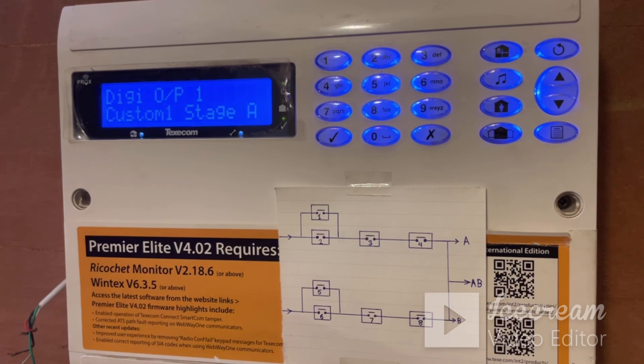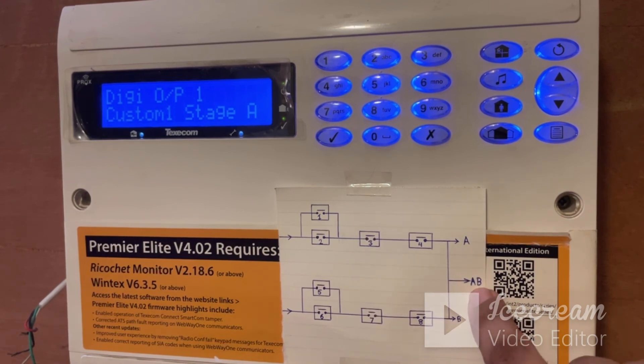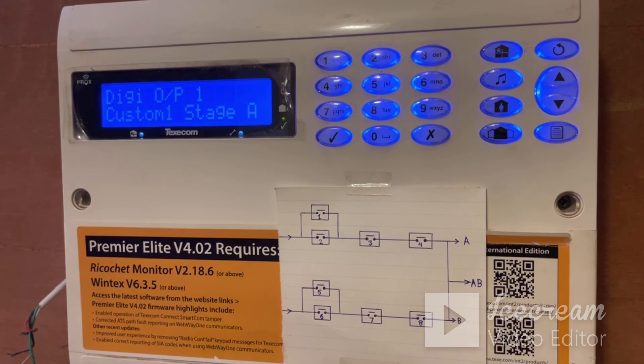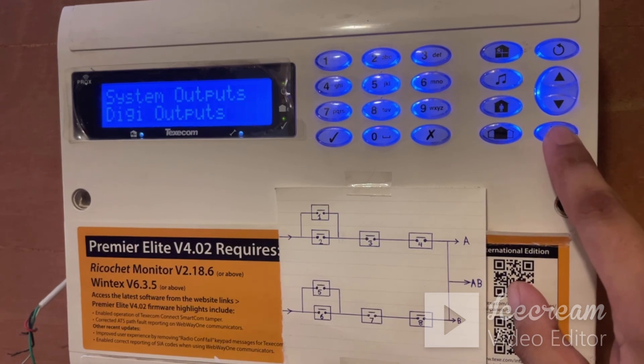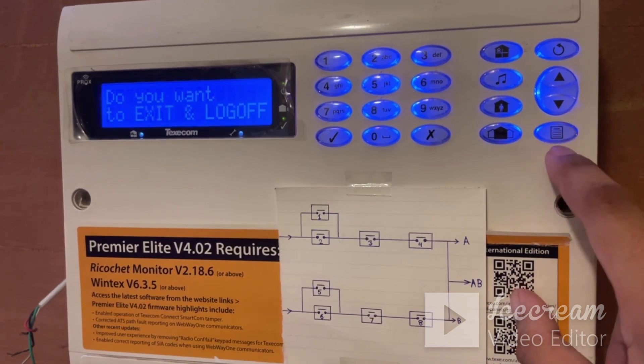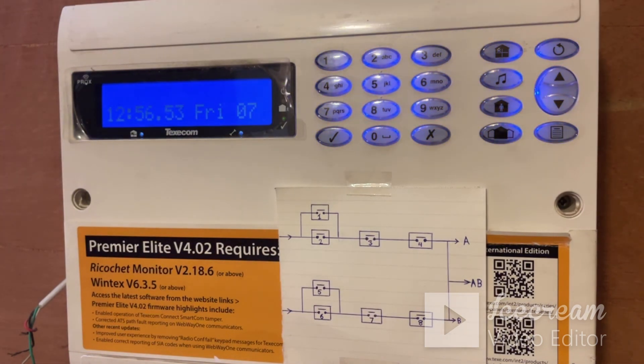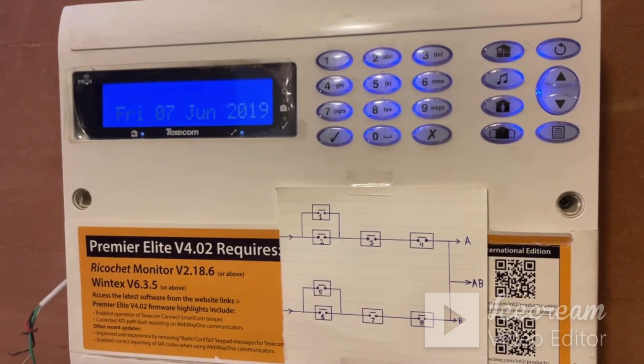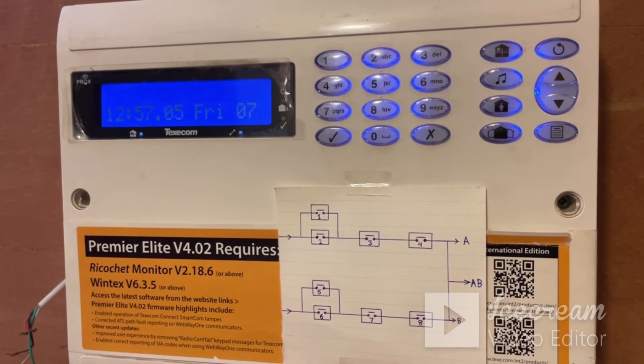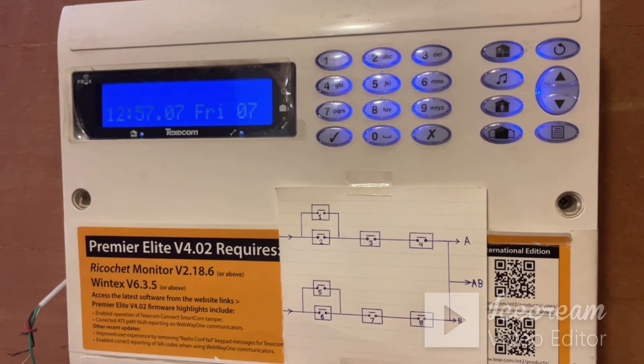Similarly, I had the option of selecting either custom stage B or custom stage AB as well, as per my requirement. Now this output is assigned and we can press menu and exit. So now what will happen — if either I get a panic silent alarm or a guard alarm, my digi output 1 will be activated. There is an OR logic implemented in digi output 1. That's all friends, thank you.